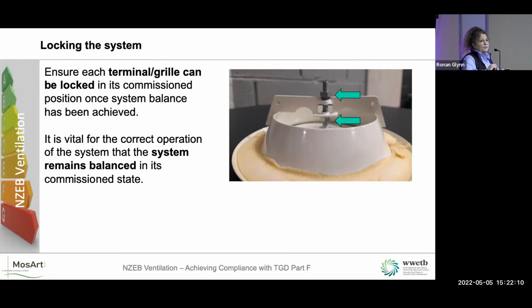nuts to each other, and then now you can't move the disc, because I guarantee you people come along to clean them, especially the extract, because dust and dirt sticks to them. So they try to clean them, and what are they doing? They're changing the flow. It's vital for the correct operation of the system that the system remains in balance once it's been commissioned.